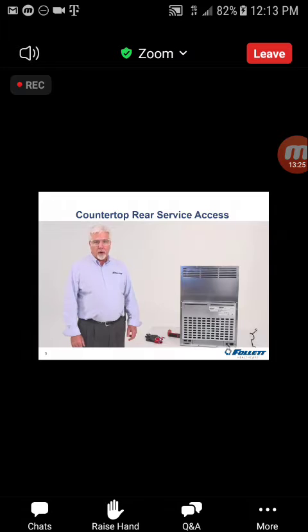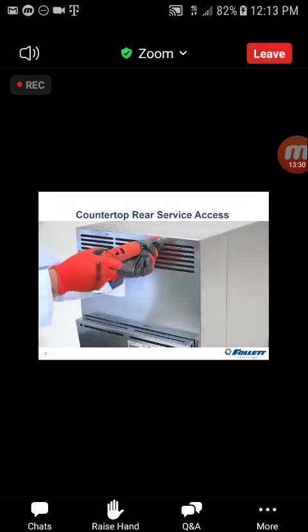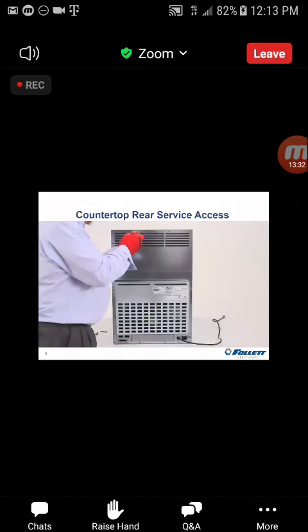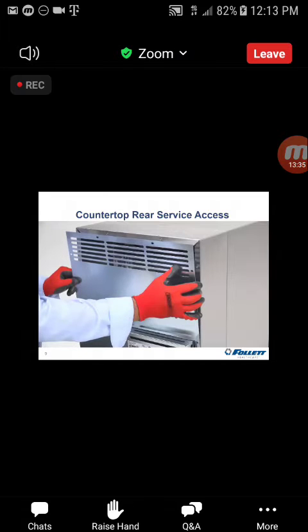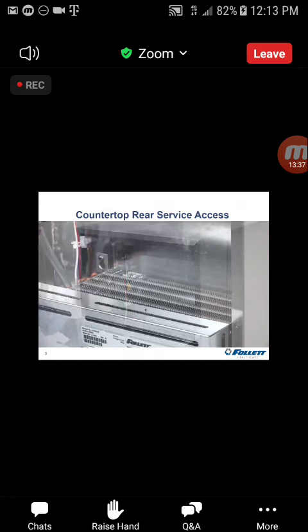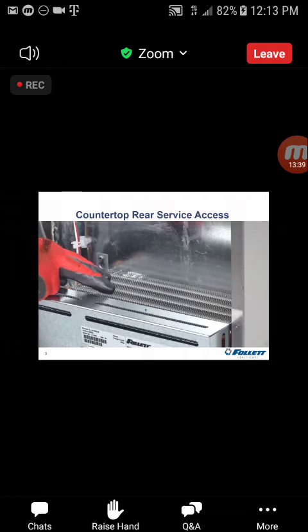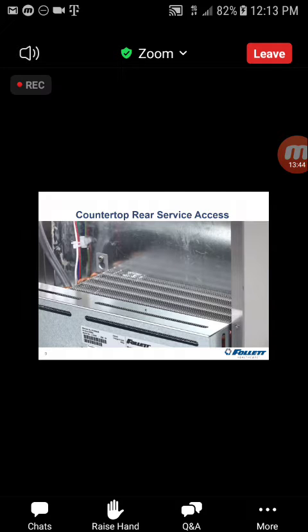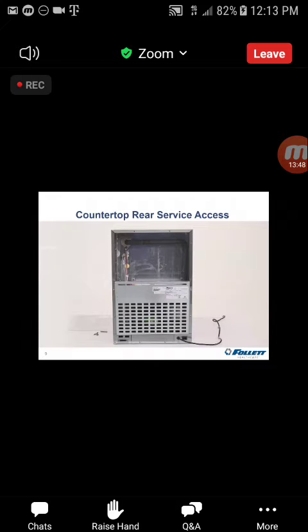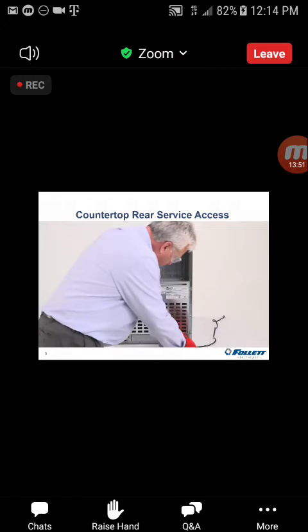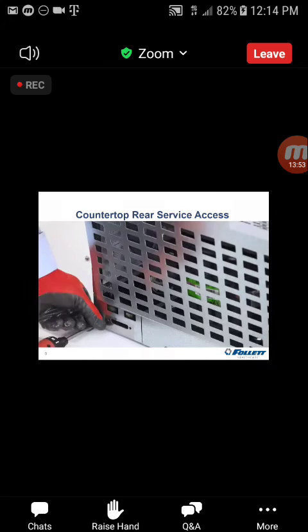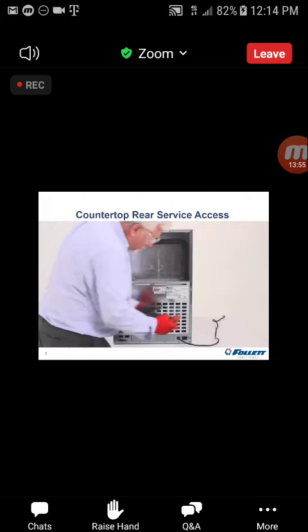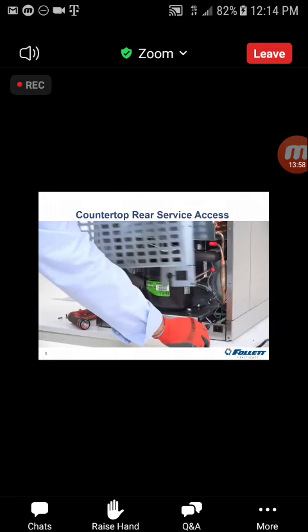Follett countertop refrigerators and freezers draw the cooling air for the air-cooled condenser in at the top of the upper service panel. In order to clean the condenser, remove the upper service panel, and that will give you access to the air-cooled condenser. You can go in with a shop vac with a brush attachment to remove the dirt and the lint from the condenser. Follett recommends deep cleaning the condenser with compressed air every few years. For further service work, the lower service panel can be removed, and if need be, the service wrap that goes around the entire unit.